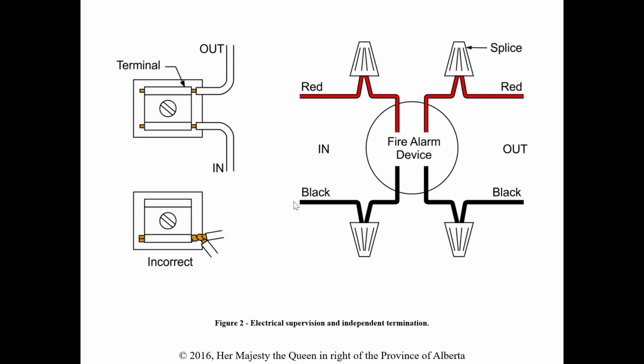The electrical supervision part of it, again, this is through the code, and it's saying that each conductor within a fire alarm system be independently terminated so the electrical supervision circuitry works correctly. So what they're getting at is if I have it terminated like this without a splice like here, if that device gets removed, I now have an open in my circuit. So then my panel's going to know there's an issue and it's going to go into trouble because it's not going to have a complete path through that, potentially through the end of line resistor, or depending on, I guess, whether it's a class A or class B.